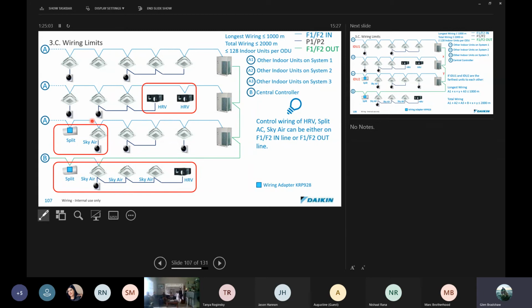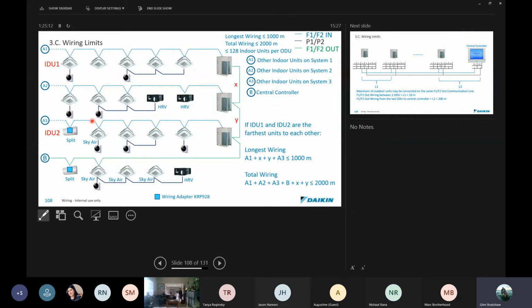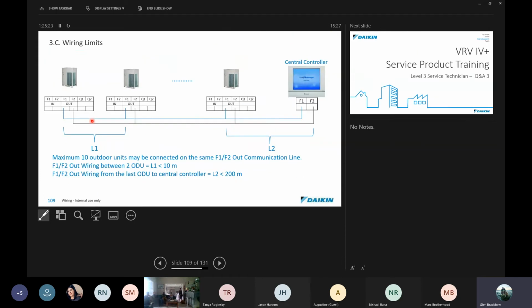Okay, control wiring of the ventilation equipment. The Sky Air can either be on the F1, F2 indoor or F1, F2 outdoor line. Right, and as we said, keep in mind those wiring limits there. Okay, a maximum of 10 outdoor units may be connected to the same F1, F2 outdoor communication line.